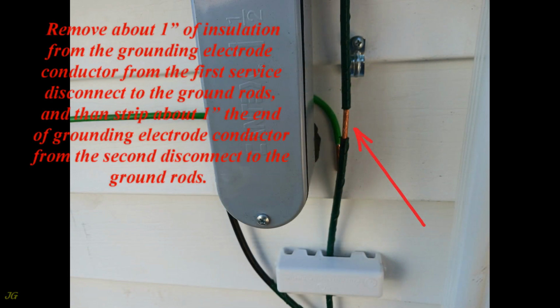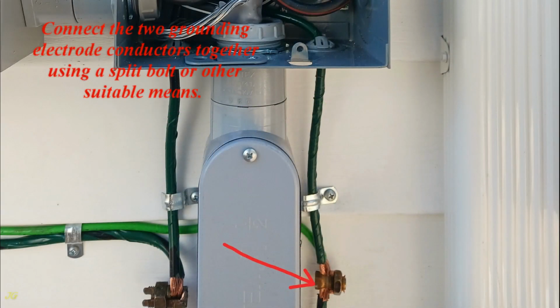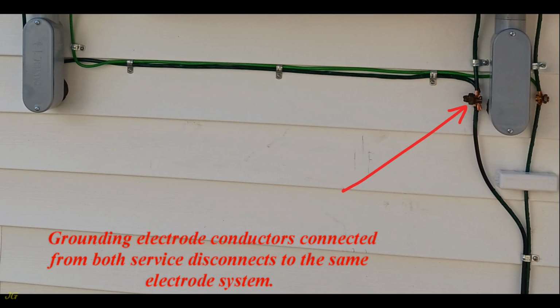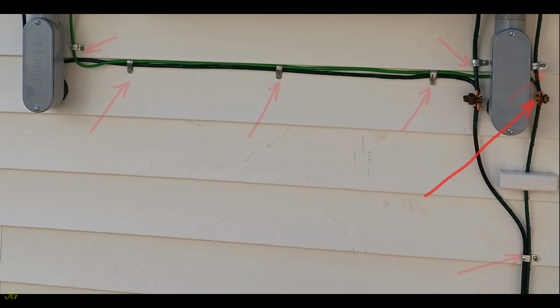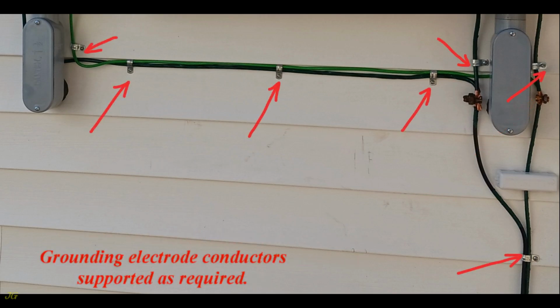Remove about 1 inch of insulation from the grounding electrode conductor from the first service disconnect to the ground rods, and then strip about 1 inch of the end of the grounding electrode conductor from the second disconnect to the ground rods. Connect the two grounding electrode conductors together using a split bolt or other suitable means. Grounding electrode conductors connected from both service disconnects to the same electrode system. Grounding electrode conductors supported as required.